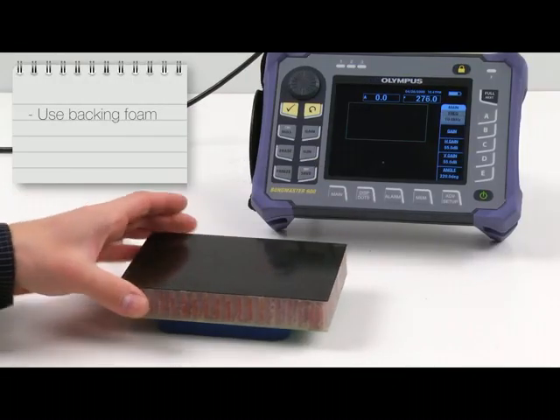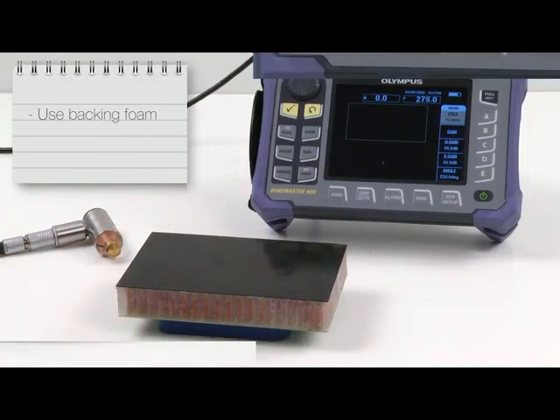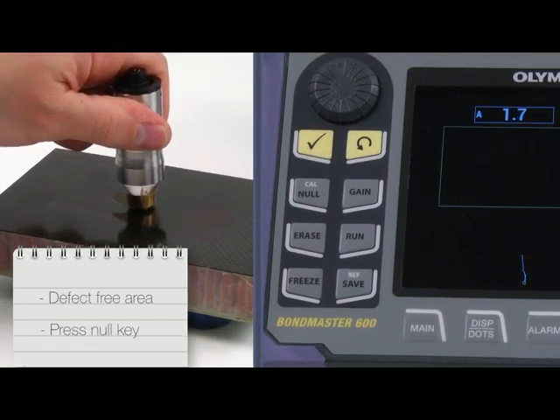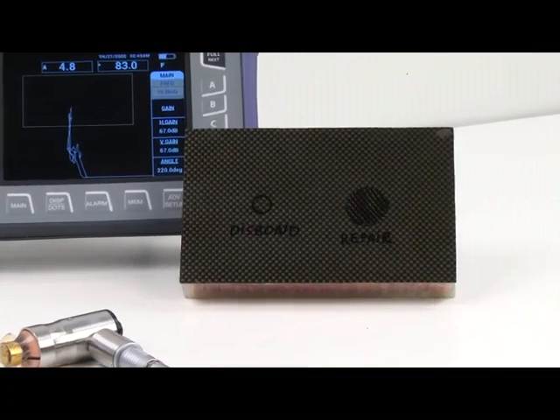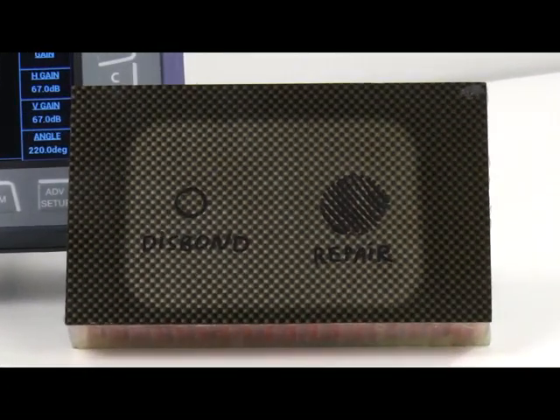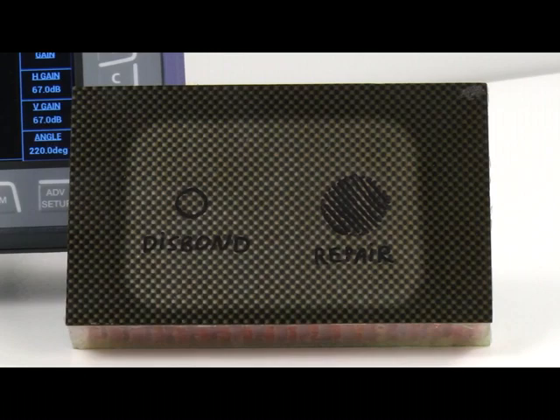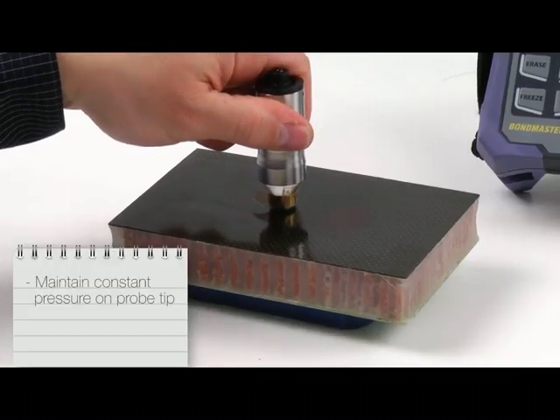You may use backing foam to achieve better results. Place the probe on an area free of defects and press the NULL key. It's important to know where the simulated defects are located to avoid mistakes during calibration.